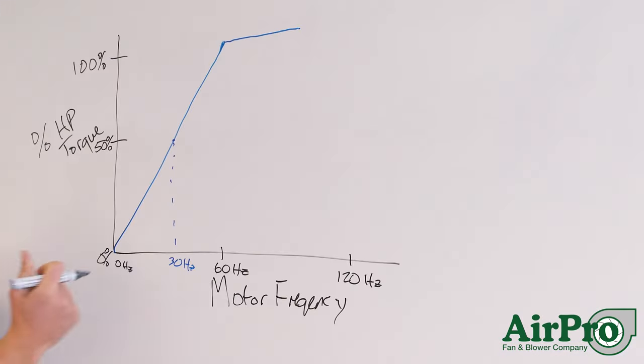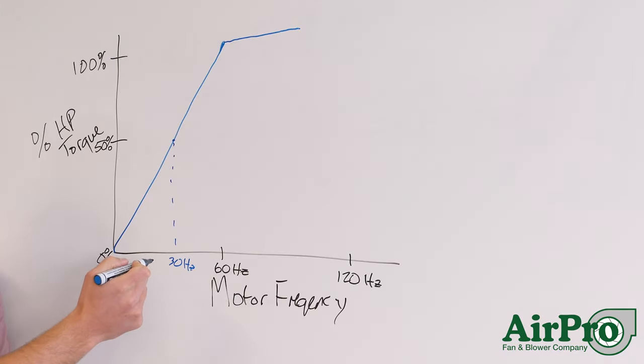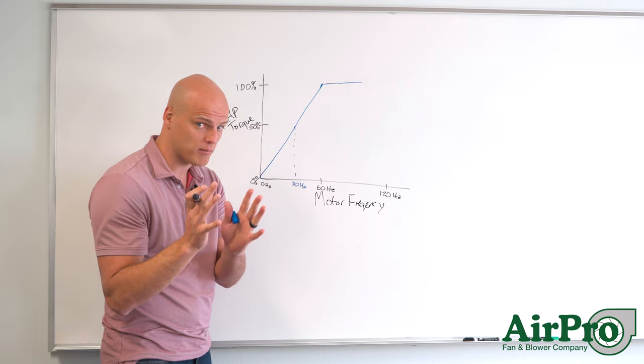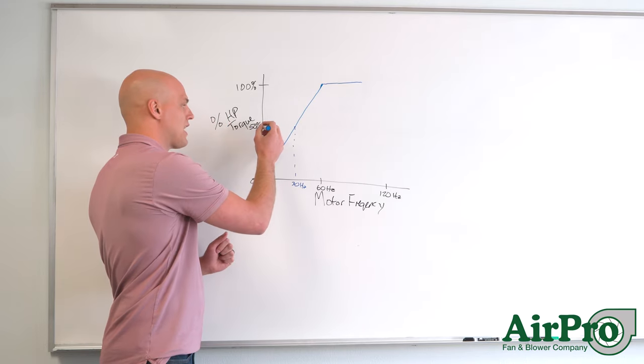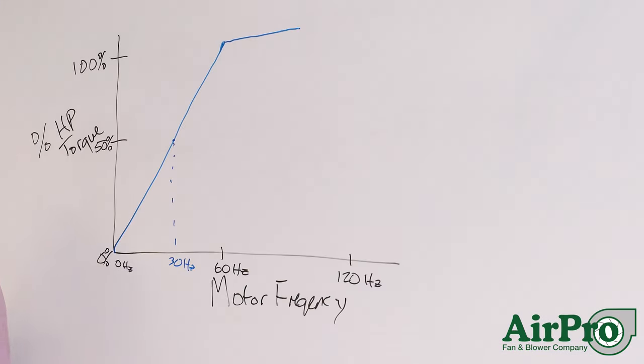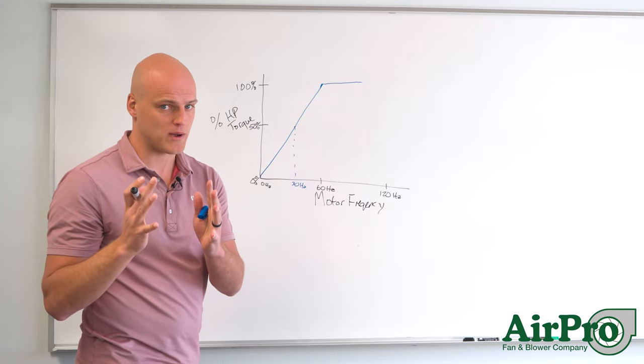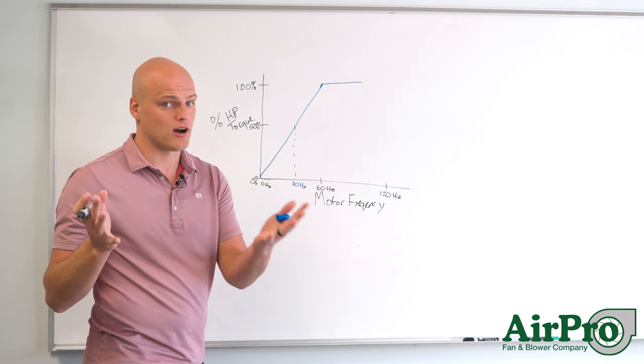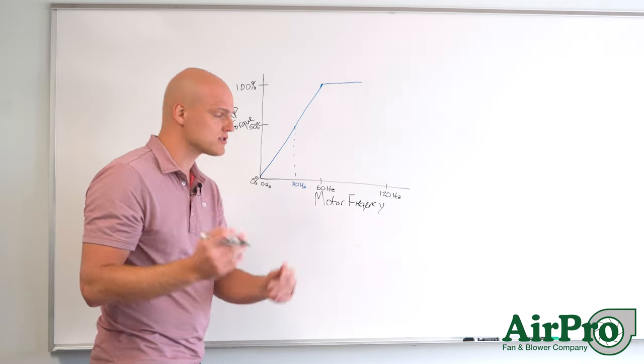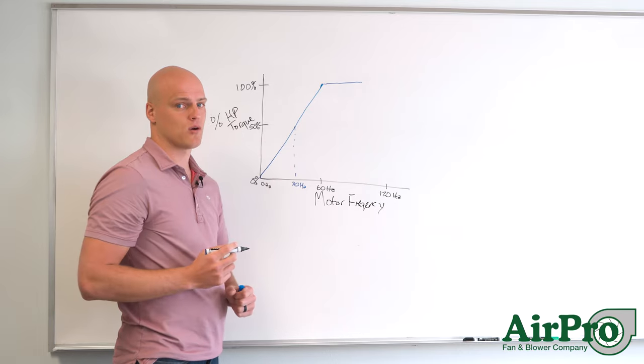But you now reduce that to 30 hertz so you're running approximately 900 rpm. You only have 50 percent of the available horsepower. Which means on a 100 horsepower motor at 30 hertz you would have 50 horsepower available.